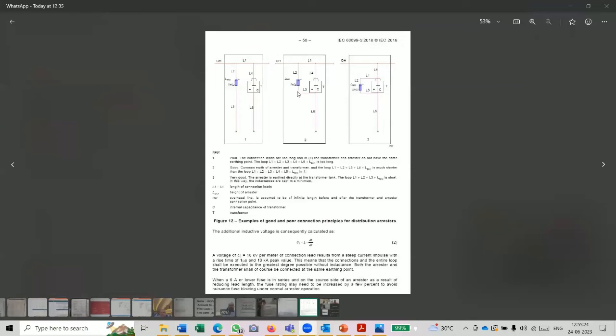Sir, I have another question. For these lightning arrestors, suppose in a structure we have six lightning arrestors. These lightning arrestors are going to six lightning earth pits, and all these earth pits are connected together through an earth grid. Now, there is a separate earthing grid also for the electrical earthing. Can the electrical earthing and this lightning earthing grid be connected together, meaning on the same earth grid? That means I connect my lightning earth pit as well as the electrical earth pit, or I have to prepare two separate earth grids and then bond them together.